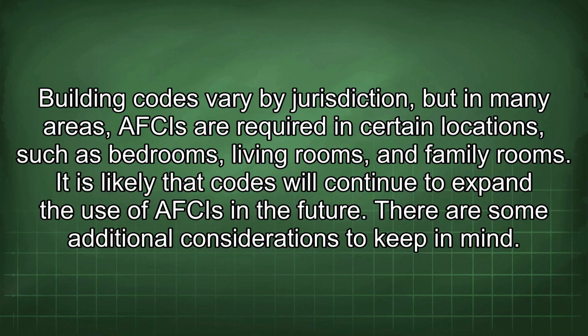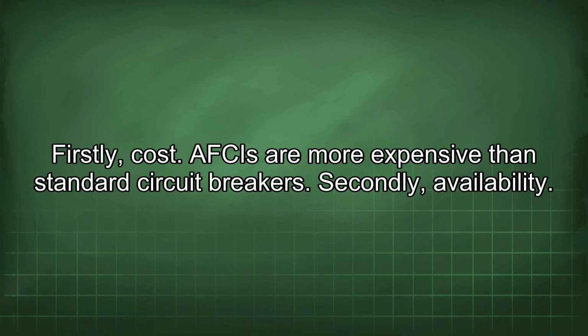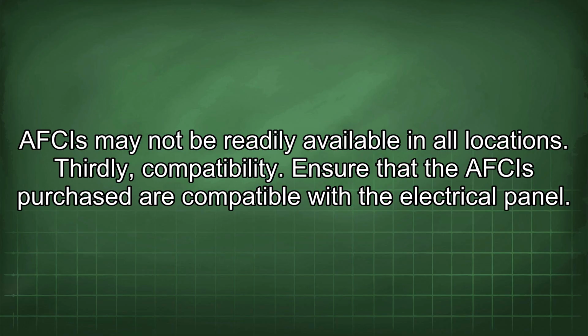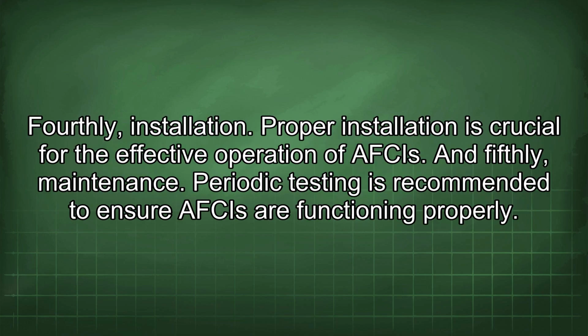There are some additional considerations to keep in mind. Firstly, cost. AFCIs are more expensive than standard circuit breakers. Secondly, availability. AFCIs may not be readily available in all locations. Thirdly, compatibility. Ensure that the AFCIs purchased are compatible with the electrical panel. Fourthly, installation. Proper installation is crucial for the effective operation of AFCIs. And fifthly, maintenance. Periodic testing is recommended to ensure AFCIs are functioning properly.